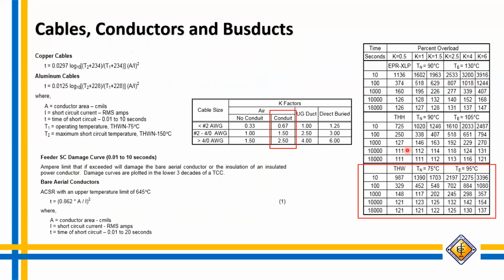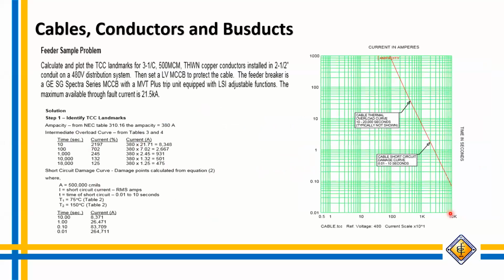So yan, cable damage curves. Mamaya may papakita ko, but this is under ABC of coordination. So hinighlight ko na lang itong in red kasi ito yung gagamitin ko mamaya sa example of the plotting of the cable damage curves. So depende yan kung no conduit or nakakonduit yung K-factors mo. Magkaiba rin sa underground duct as well as direct buried. So mamaya meron akong example. Pakita ko mamaya yung basic calculation natin using this formula.